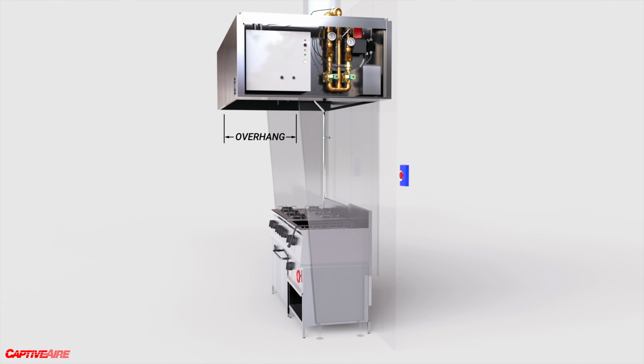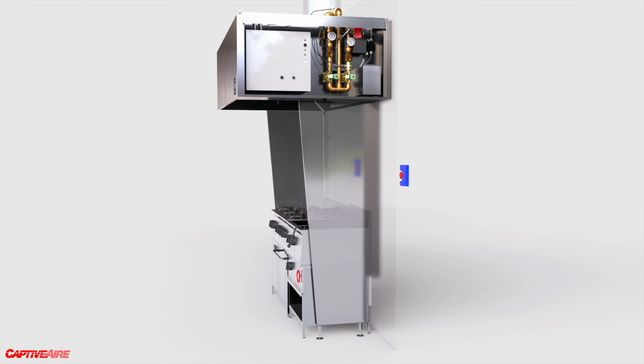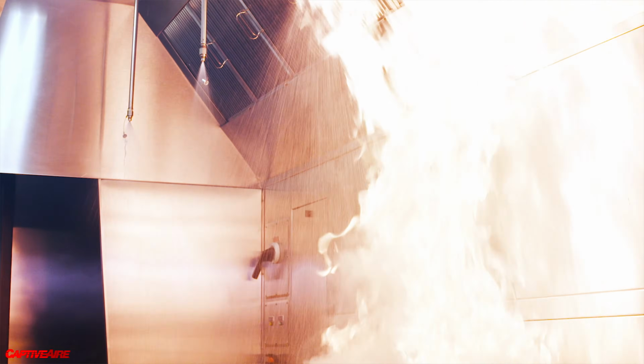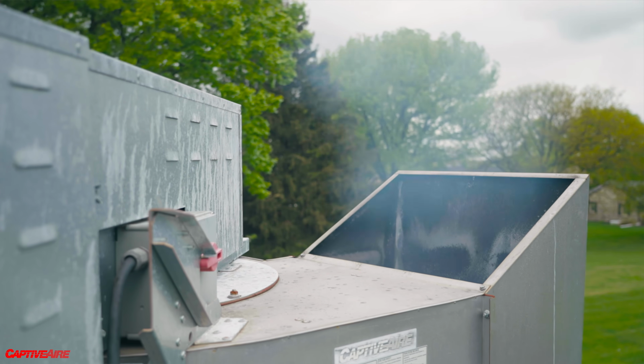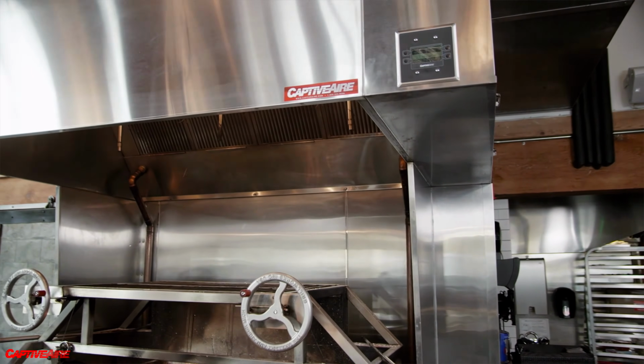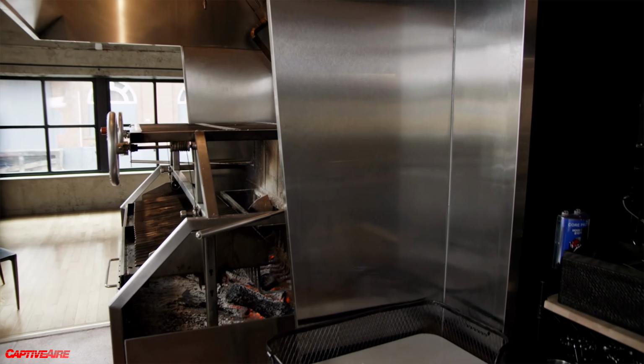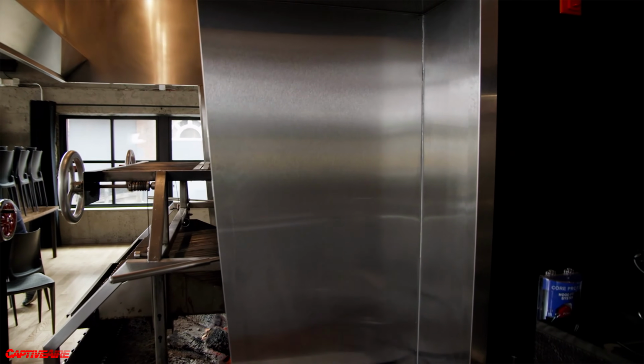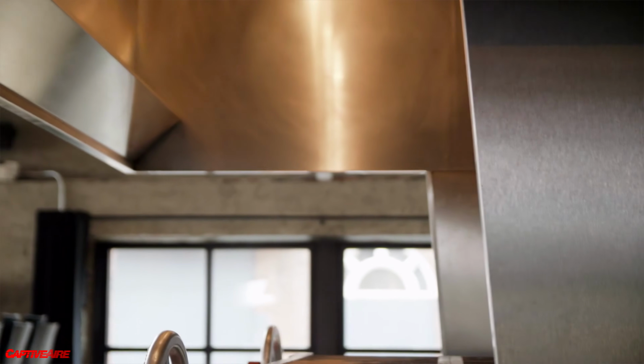That would be your overhangs on your appliances - your hood is slightly larger than the appliance - and we also have options for end panels, which both keep the fire in and reduce the overall CFM you would need for that hood. Vertical end panels are very important for passive fire protection. The challenge is how they fit within the cooking operation - some people may view it as an obstruction, which it absolutely is. It's an obstruction to a fire spreading in the building.